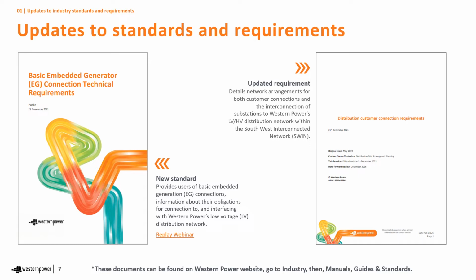There have been 2 standards recently published in December. The first one was the basic embedded generator connection technical requirements. This provides everything you need for connecting an embedded generator, an inverter energy system typically, to a standard connection service on the Western Power network. In addition to that, we've also updated the distribution customer connection requirements, and these provide the installation arrangements, wiring sample examples for you to work out how to connect and arrange your installations.